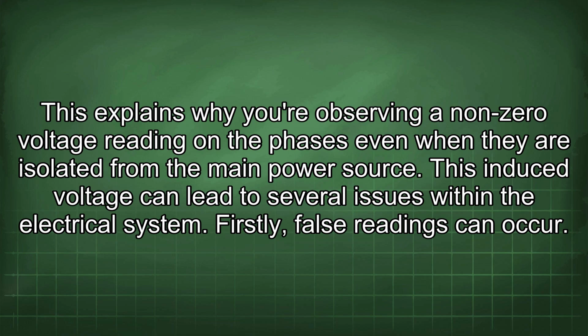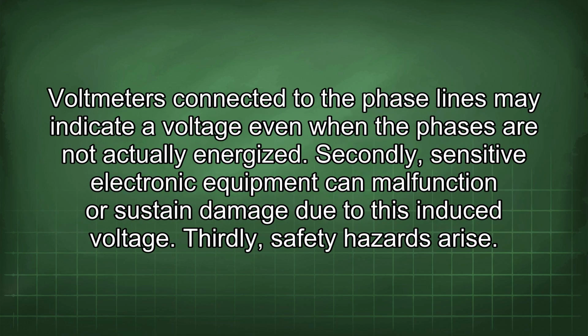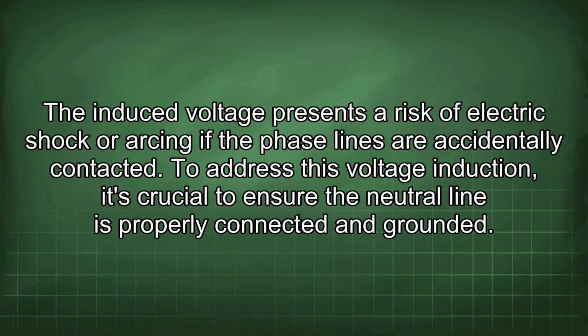Firstly, false readings can occur. Voltmeters connected to the phase lines may indicate a voltage even when the phases are not actually energized. Secondly, sensitive electronic equipment can malfunction or sustain damage due to this induced voltage. Thirdly, safety hazards arise. The induced voltage presents a risk of electric shock or arcing if the phase lines are accidentally contacted. To address this voltage induction, it's crucial to ensure the neutral line is properly connected and grounded.